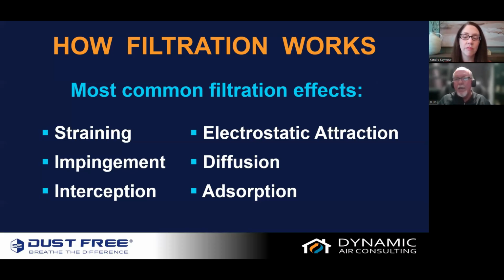So the electronic air filter, which we talked about, kind of antiquated technology, has an electronic element that gets energized. And so then we have the air that goes through a pre-filter. And there's two types that would either trap those particles on the element, or some of them would actually zap them, and they sound like a bug zapper, and it's actually breaking those particles down from larger particles to smaller particles. The problem with those is that when the system turns off and that electronic element is de-energized, there's nothing holding those particulates anymore. And then upon initial startup and you get that blast of air, a lot of that stuff will kick loose until we can start having more attraction.